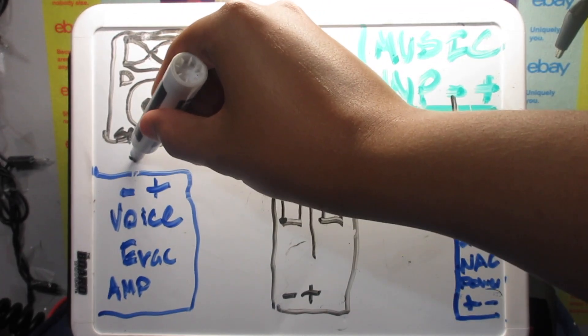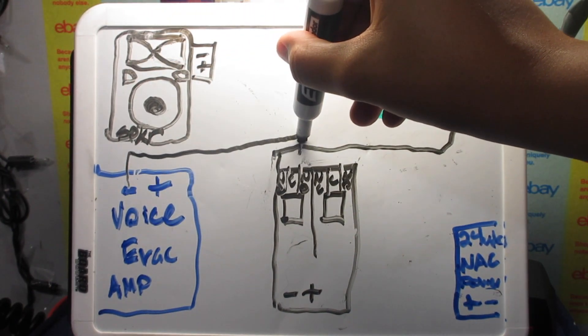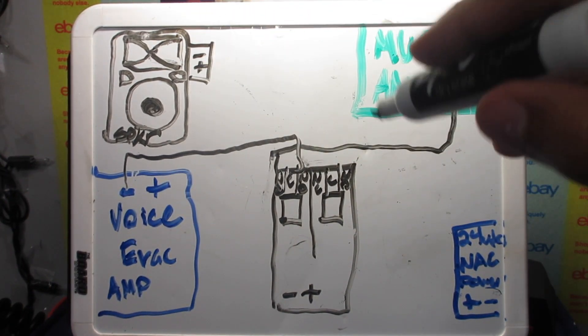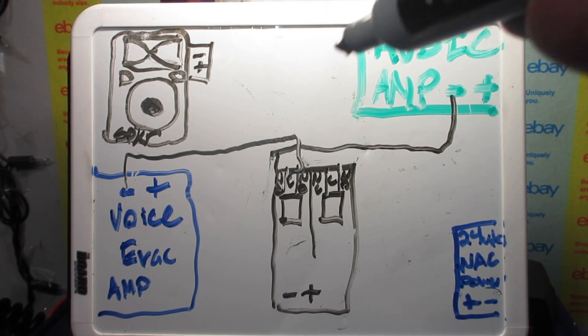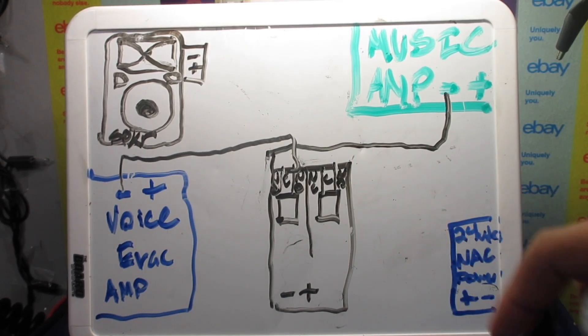Then we take our voice evac negative and bring it to the normally open because we want it to not be playing music or voice evac sounds when the panel isn't activated or when there's no power to the relay.